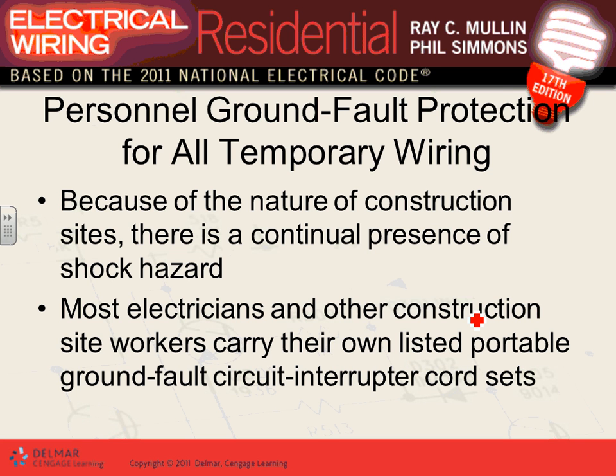The last thing, temporary wiring GFCI. The NEC code book does require that if you're doing temporary wiring, like construction, carrying on a job, 15, 20, and 30 amp, 120 and 240, 120-volt receptacles must be GFCI protected. So 15, 20, 30 amp, 120 and 240/120 receptacles must be GFCI on a construction site. And why do you think we care about putting GFCI on a construction site? Because we don't want to kill the electricians, right?